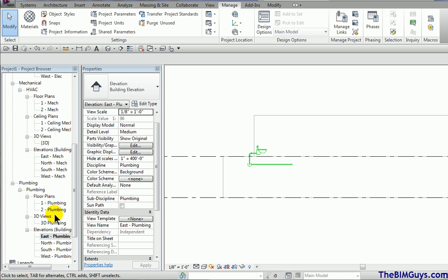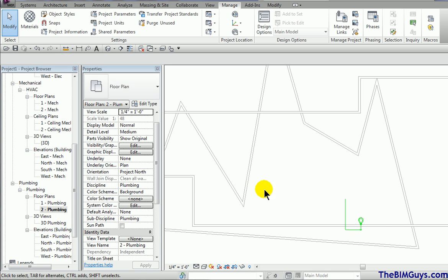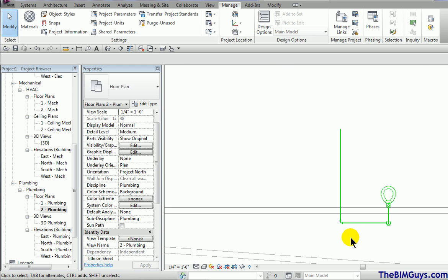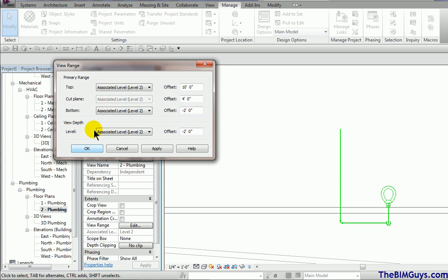Back to our plumbing plan, we're on the second floor. We want to show the pipes that go below the floor. So we go over and adjust the view range. I scroll down and click on view range. I set it to negative two feet and then I have to set this to negative two feet because Revit forces me to do that. We hit okay.